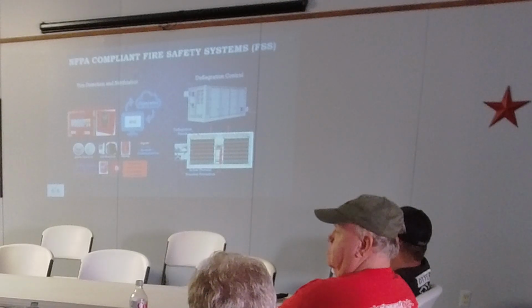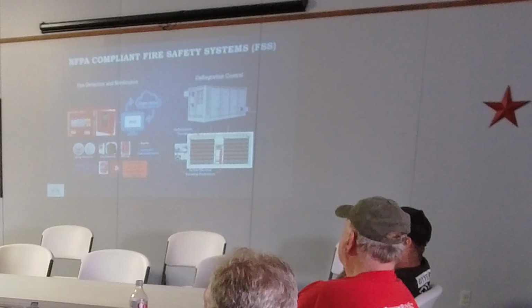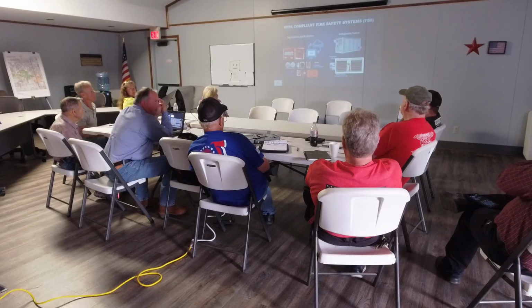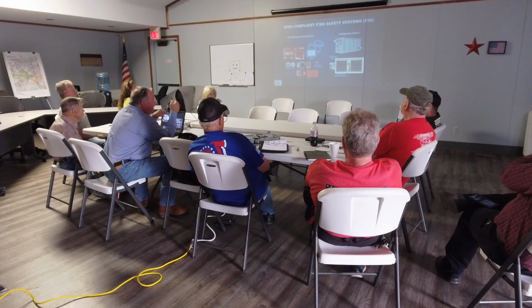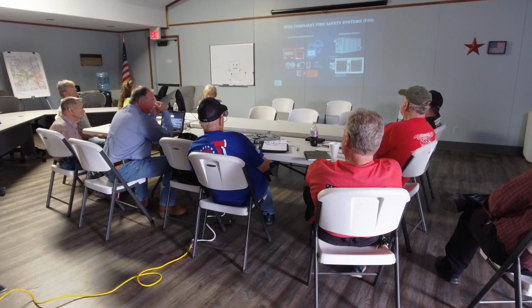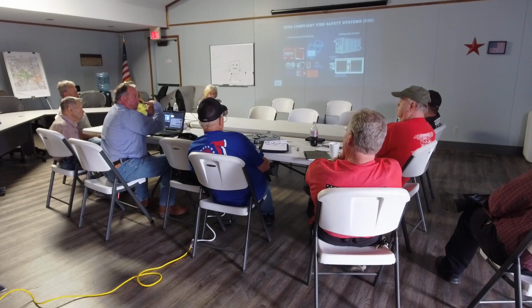Most manufacturers employ both NFPA 68, which is explosion control, and NFPA 69, which is explosion prevention. One's lagging, one's leading. The lagging one, NFPA 68, is done with what they call a partial deflagration panel, like a rupture disc. At a certain pressure it ruptures and allows pressure to escape. Sometimes they'll use a weighted door that cracks open, and once the pressure drops, it falls back down.